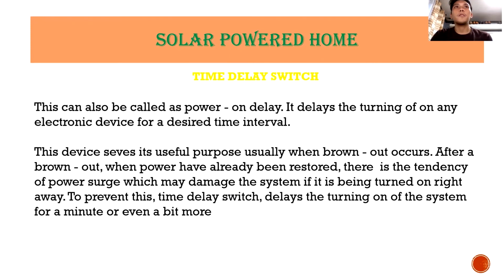So ano yung time delay switch? This can also be called a power on delay. It delays the turning on of any electronic device for a desired time interval. This device serves its useful purpose usually when brownout occurs. After a brownout, when power has already been restored, there is the tendency of a power surge which may damage the system if it is turned on right away. To prevent this, the time delay switch delays the turning on of the system for a minute or even a bit more.